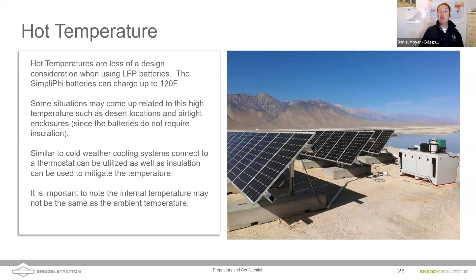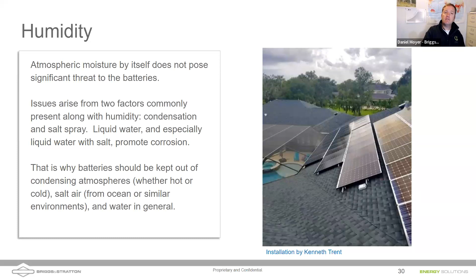So when we think about humidity, we're thinking about atmospheric moisture, and that necessarily doesn't really present a threat. What really presents a threat is when we have salt in the air, and these batteries are not hermetically sealed. So there is a possibility that over years, over time, that humidity and salt can work its way into these batteries and start to cause rust and really corrosion inside these batteries, which can create problems. So if you are in one of these situations, let's keep them inside, let's keep them as protected as possible, and keep in mind how that can affect it. Altitude as well, this has been a big issue mainly with other form factors.